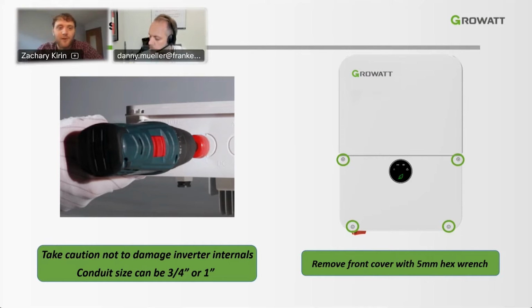Again, I would recommend doing this while the inverter is not installed. But once everything is installed, you'll need a 5mm hex wrench to loosen the 4 screws shown here. And this will give you access to the inside of the inverter, to the wiring cabinet, which I showed in the last couple slides.